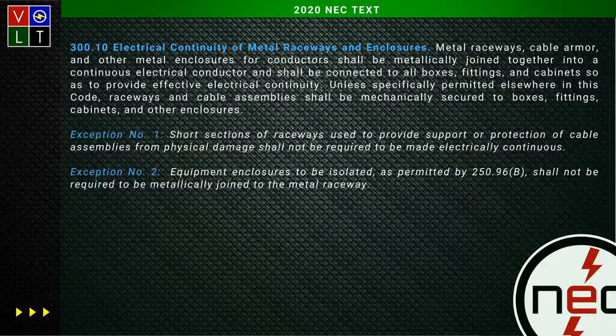What I did is I went ahead and threw a few sections here to show everybody. If you look at exception 1, where they talk about short sections of raceway, it tells you that you can use those to provide support or protection of the cable assemblies from physical damage. This is a good section to start at, giving you this type of permission.